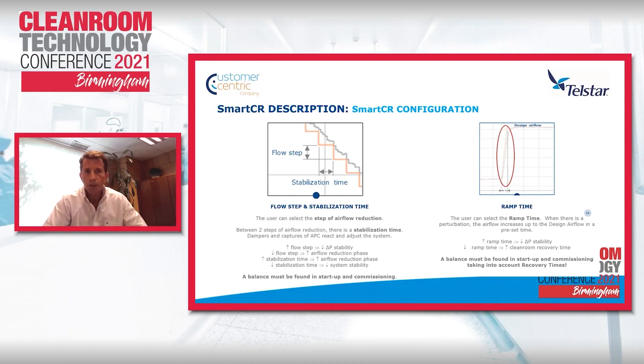If we increase the flow step, I mean, if we reduce in every step a higher amount of airflow, the differential pressure of the different rooms will be compromised. If we reduce it, then the duration of the ramp down to the minimum flow will be longer, and the opportunity to save energy will be less. If we increase the stabilization time, this ramp down will also increase, and the opportunity to reduce costs will be lower. And if we reduce the stabilization time, the system stability will be lower.